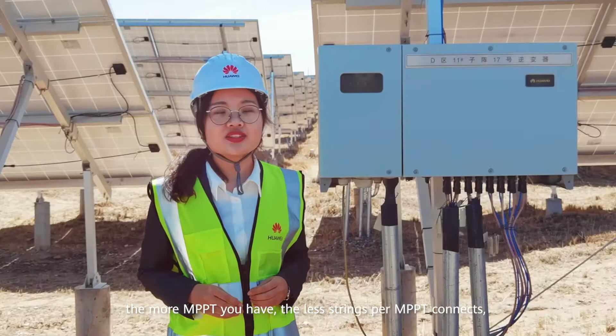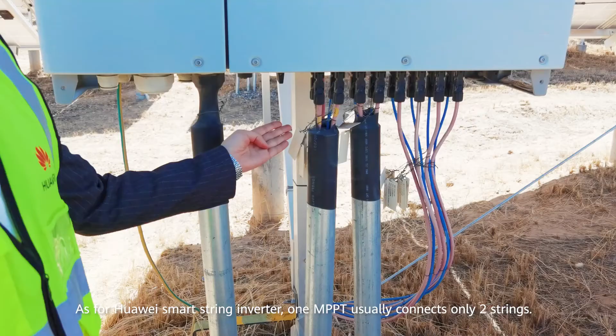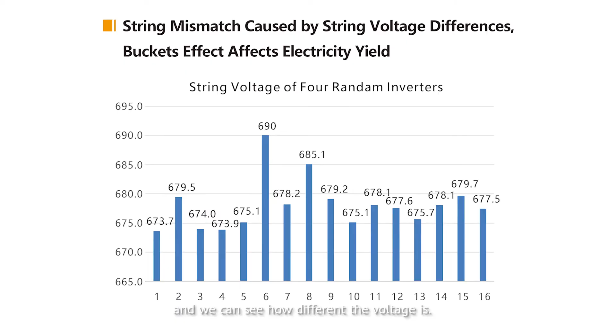This is the strength of string inverters, especially compared with the central inverter, which normally has 1 MPPT with 100 strings. As for the Huawei Smart String Inverter, 1 MPPT usually connects only 2 strings. Here we randomly choose 4 inverters in the same area, and we can see how different the voltage is.